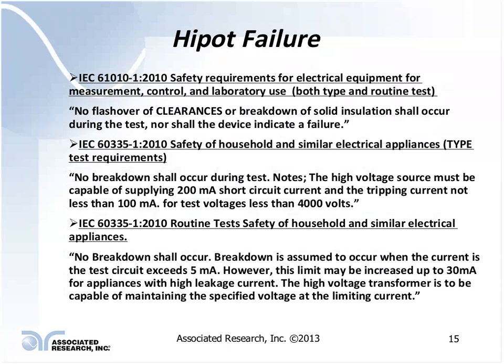Okay, let's look at some of the standards. IEC 61010-1:2010, which is the standard for laboratory equipment. Both as a type test and a routine production line test, this standard says no flashover of clearances or breakdown of solid insulation material shall occur during the test, nor shall the device indicate a failure.